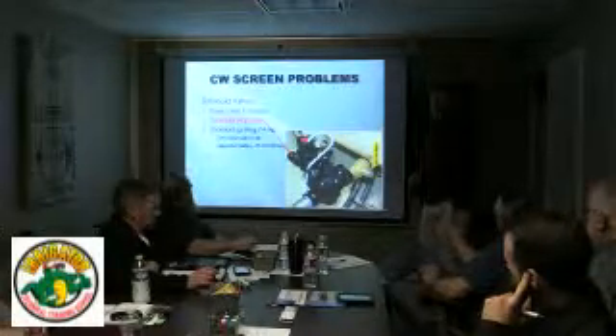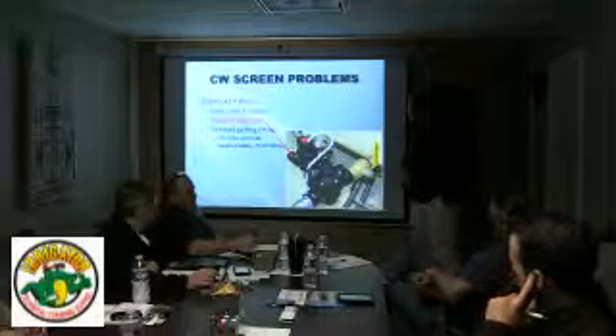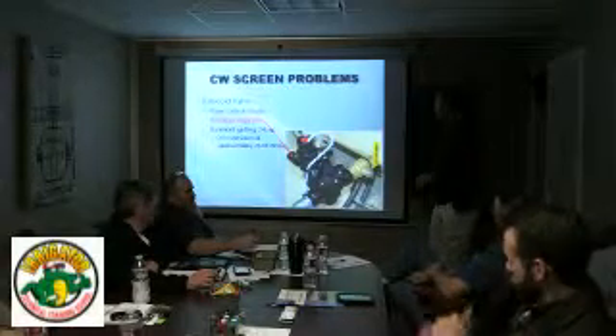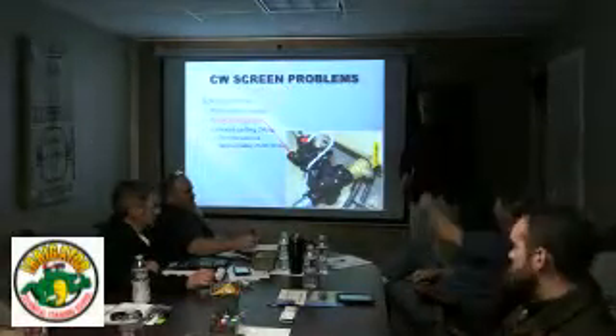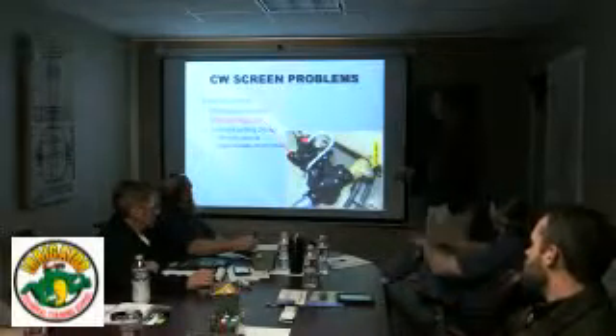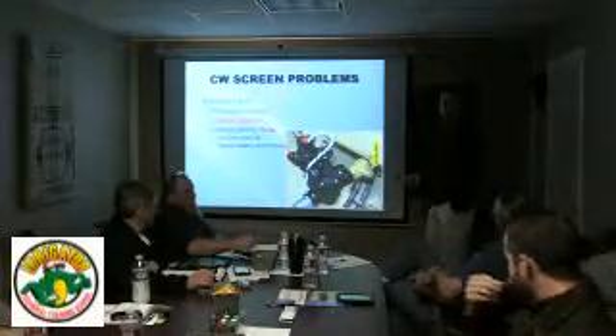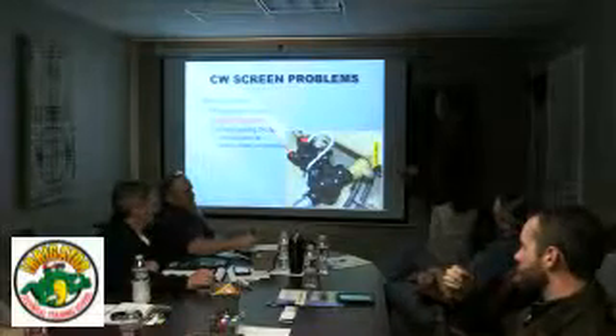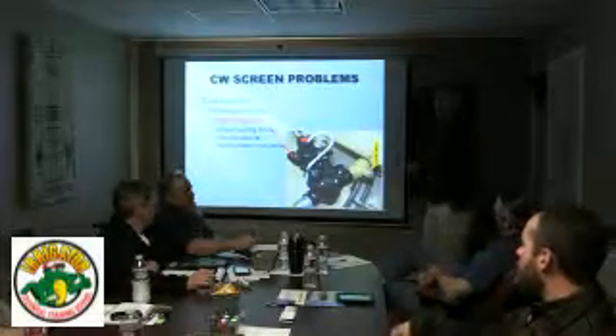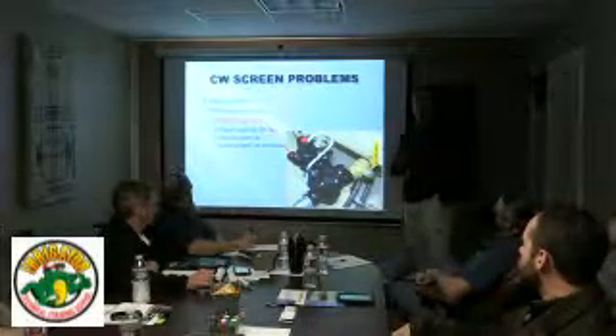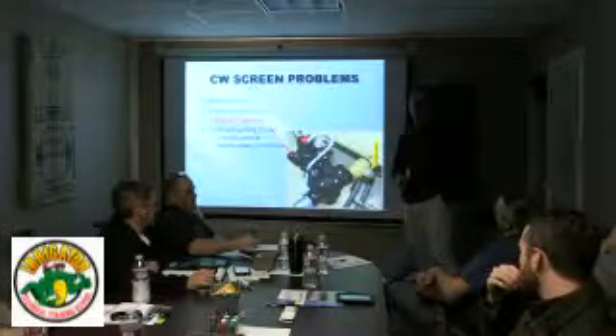And that would be the reason why you open that valve all the way up. Yeah, you want full flow, but you want it regulated to pressure. You allow that to regulate, not your dial. Yeah, we allow this to regulate it instead of the flow control. This is just a sleeve. You pull it off, you'll see a little yellow indicator with the scale, and it should be set right on 55. That is what we set it on.